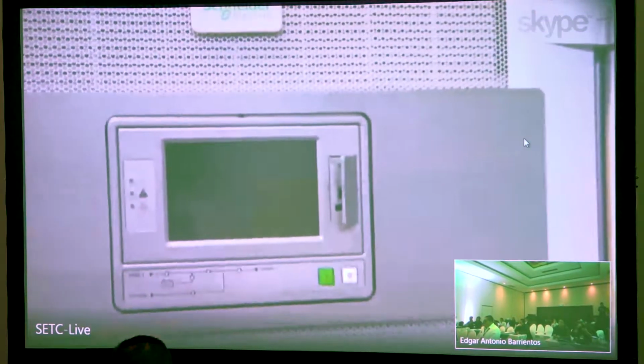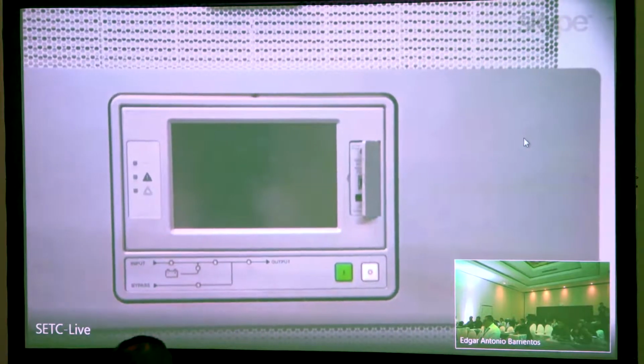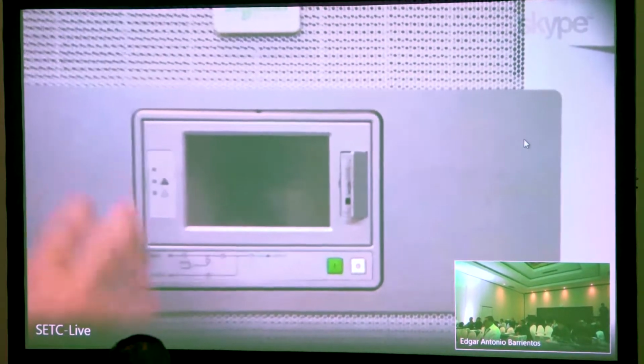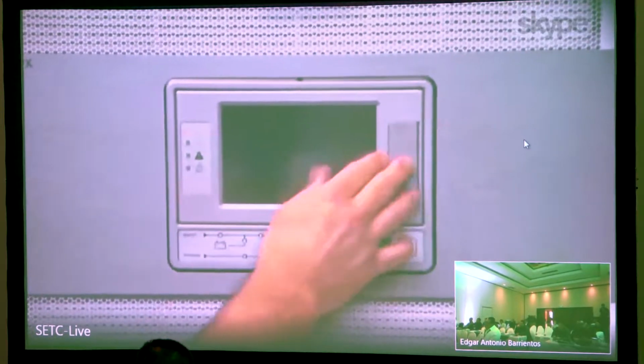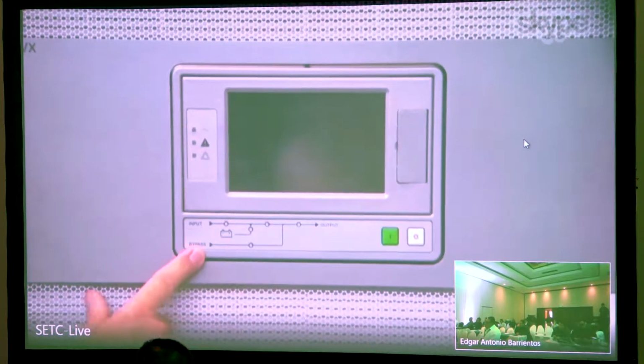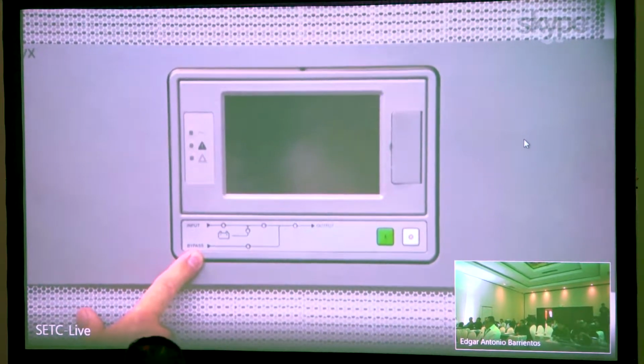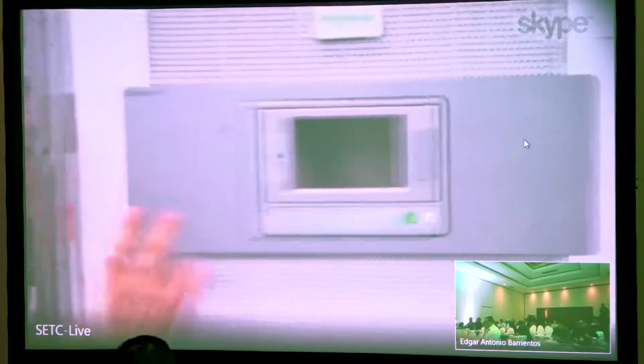I'll show you right here. This touch screen can be replaced when the unit is carrying load, because all the controls—remember where I showed you the main controller—all the controls are done there. This is just our interface, so we can replace it while the unit's online. And then we also have this second discrete operator interface. That's a differentiating factor on this UPS.